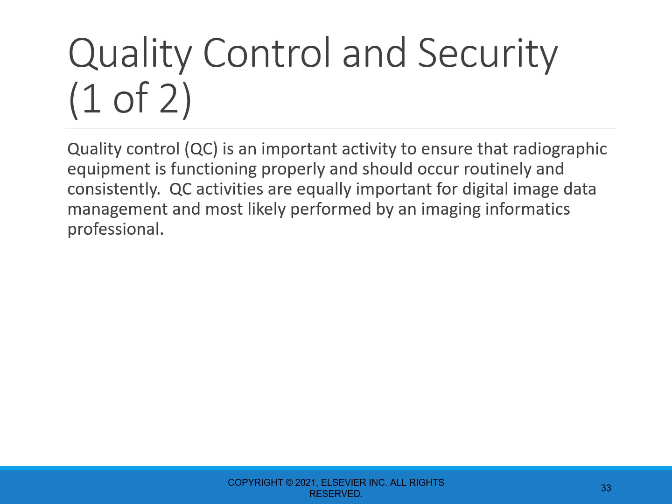As with maintaining good quality control and security of our imaging equipment, like we've talked about, we also have to practice good quality control and security of our computer systems. Quality control is an important activity that should ensure the radiographic equipment is functioning properly, including the display monitors. So not only are we going to have quality control activities for our equipment, but we're also going to have quality control activities for our displays, which I kind of started to speak about when I showed you the AAPM test tool or the SMPTE test tool. Those are some of the things that we're going to have to use to evaluate our displays.